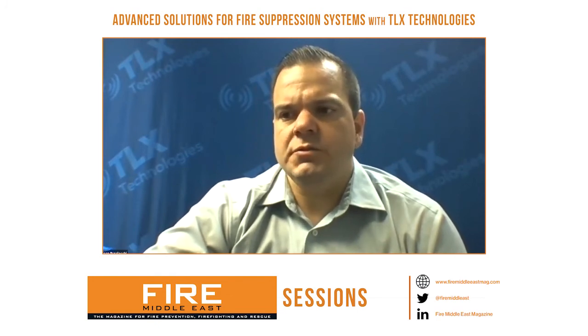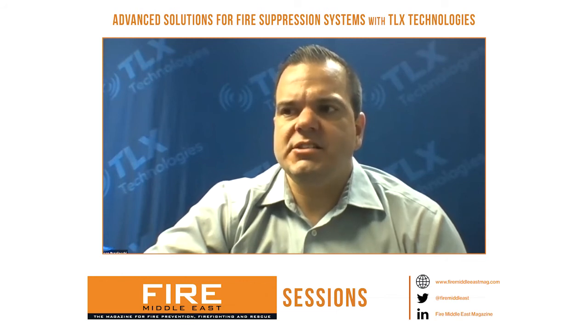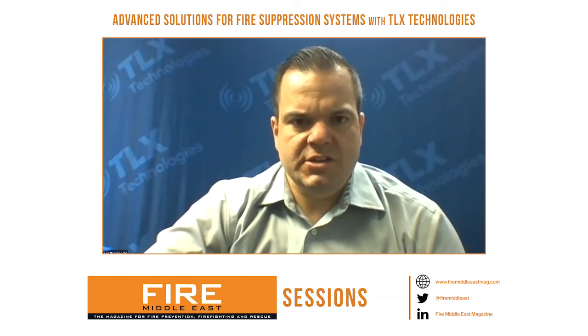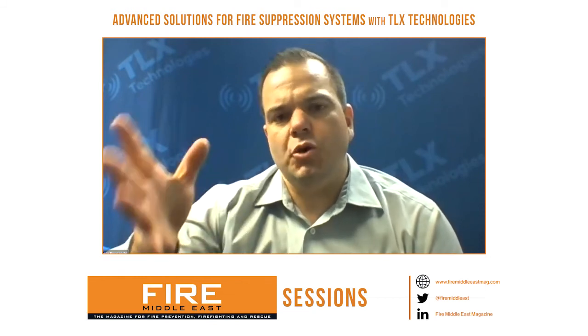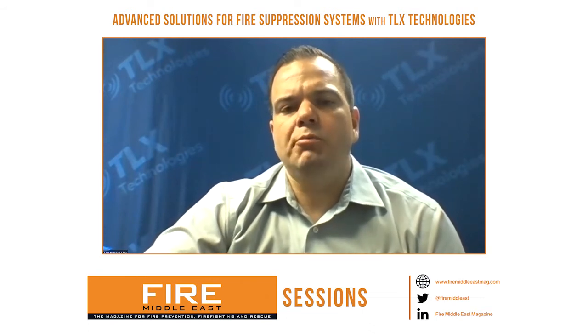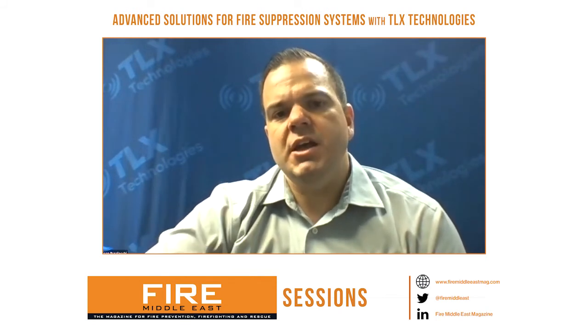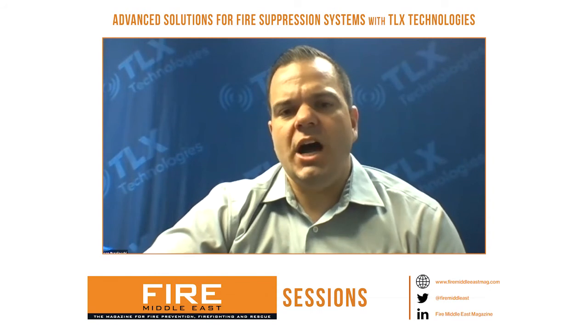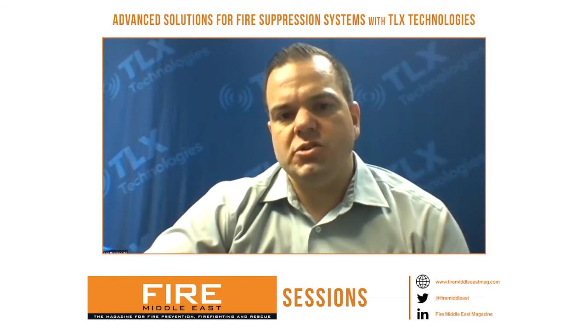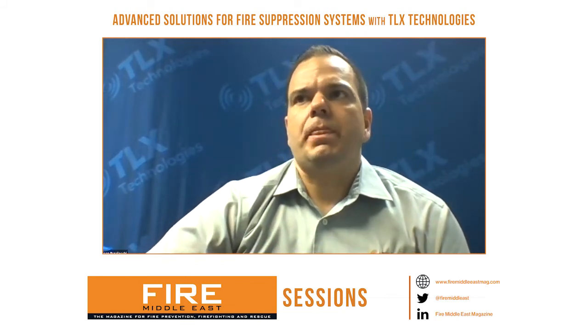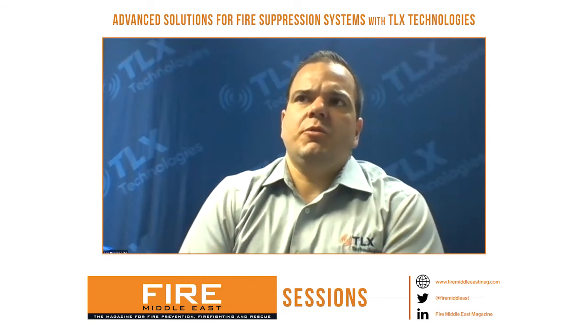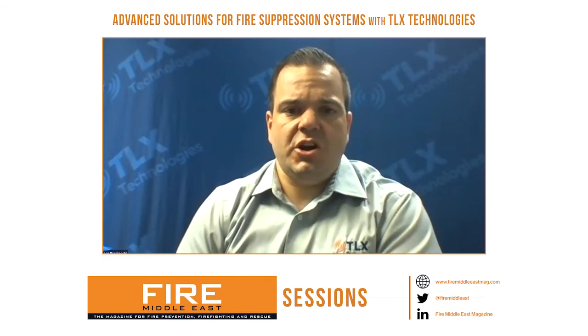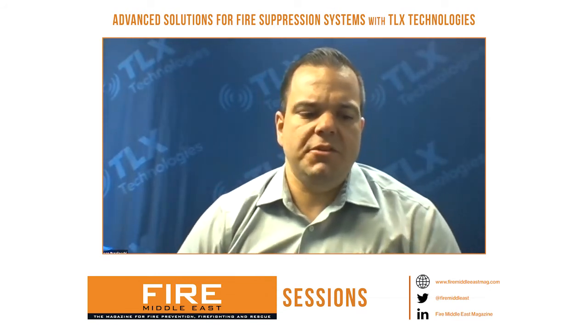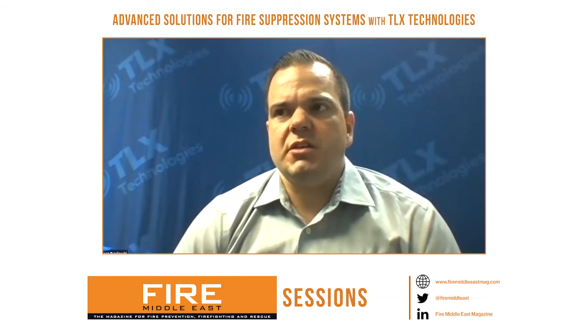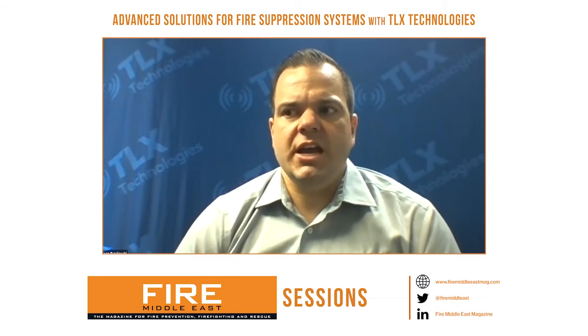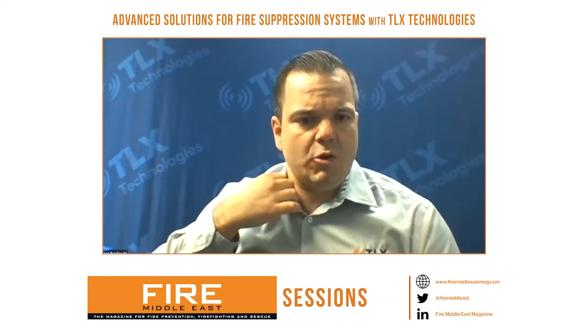So our devices themselves are engineered and then tested with the agencies, under a specific force parameter that we're putting on our print. And we have a minimum force output at the end of the travel of the firing pin that we can continuously and reliably ensure we're coming up with the same force on our device. For us, we need to know what our customers are requesting as far as force output from our device to open the discharge valves of their systems, and then we offer a product that's going to suit that appropriately. So we're going to be able to reliably create a device that puts out the force outputs that's going to be requested.